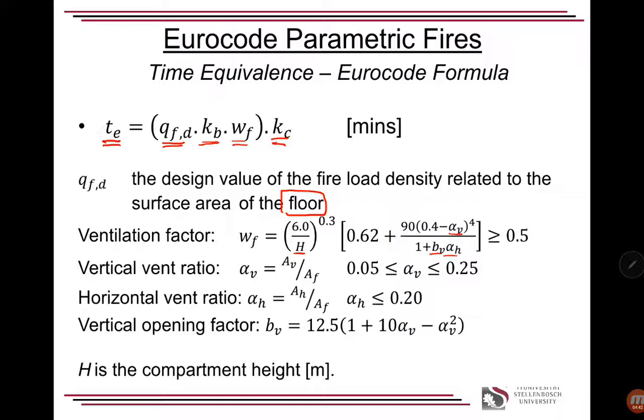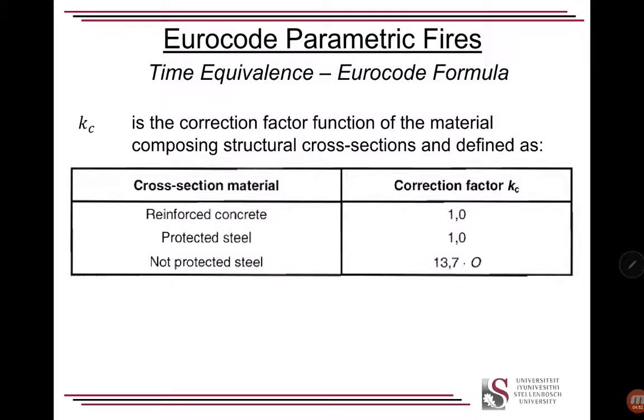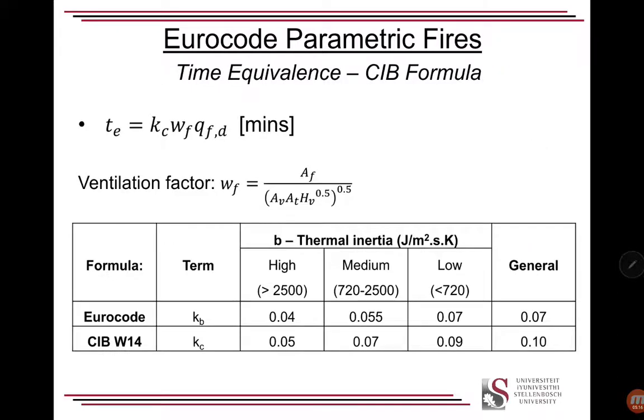And then we've got a vertical opening factor. And you'll once again see that this is quite an empirical factor to adjust. So this is based upon testing and some curves are being fitted. And you always should be cautious of applying empirical equations without understanding where they come from. We've got a kc, a correction factor, which is a function of the material composing structural cross-section and defined as: if you've got one for reinforced concrete and protected steel, and then if it's not protected, so you've got a function of the ventilation area O. So we need to adjust our equation using those.